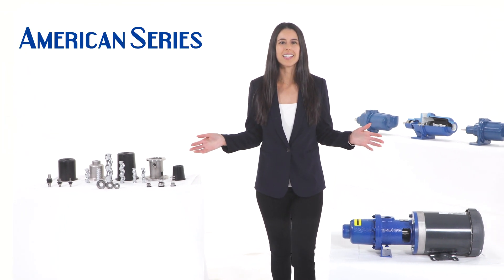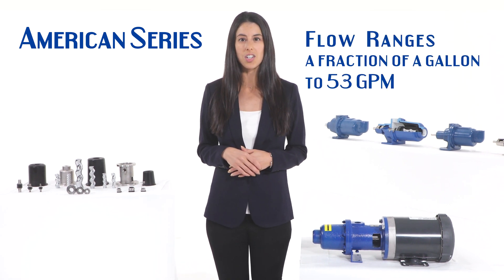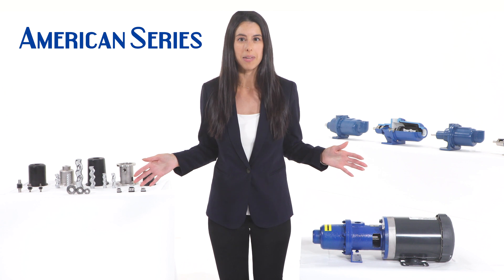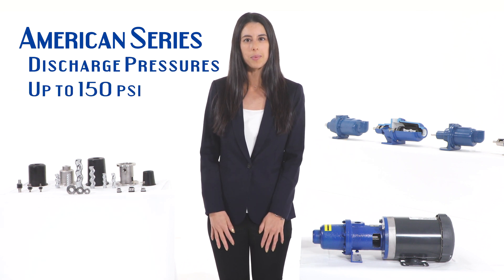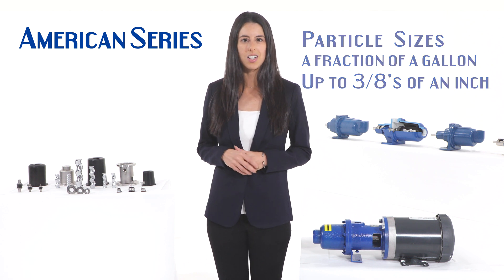Our wobble stator design is available in six different rotor-stator configurations and handles flows from a fraction of a gallon up to 53 GPM and discharge pressures up to 150 PSI. It can also handle particle sizes up to 3/8 inch.